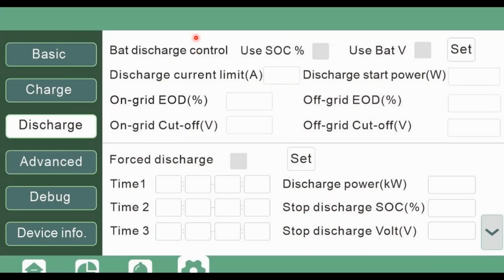On the discharge section, it's pretty much the same as the AC: you set it to SOC, discharge current limit. Here you would use our recommended discharge settings based on our data sheet. And then you have your on-grid end of discharge. Basically, you can regulate these to go from 90% all the way to almost 5%, based on your on-grid end of discharge. That would mean that when the battery reaches a certain state of charge, the grid will kick in to provide the existing loads. Same with your off-grid for off-grid scenarios.